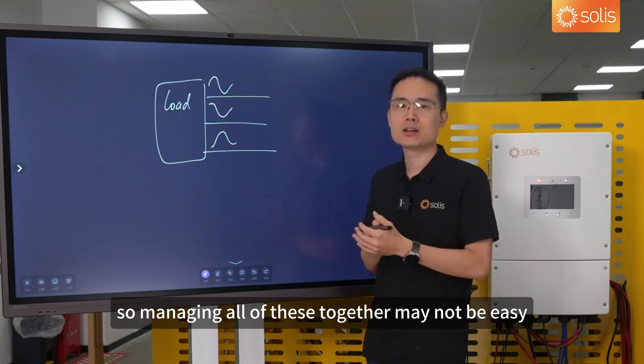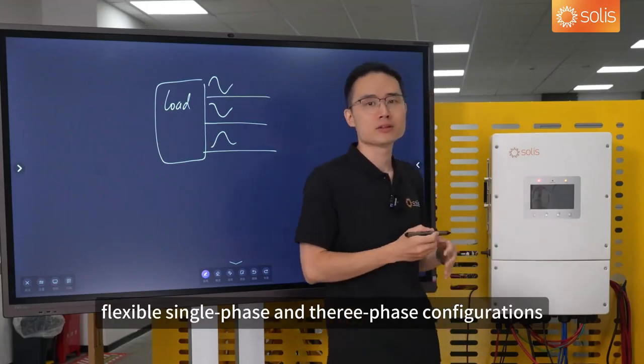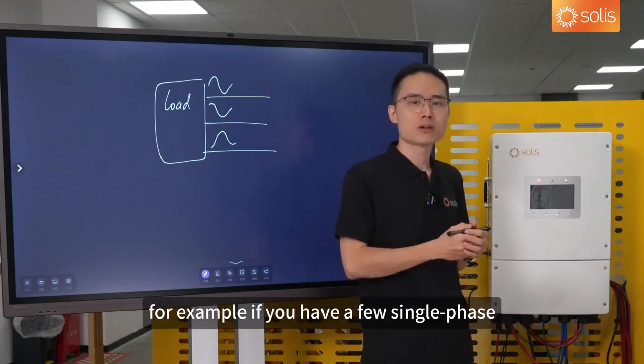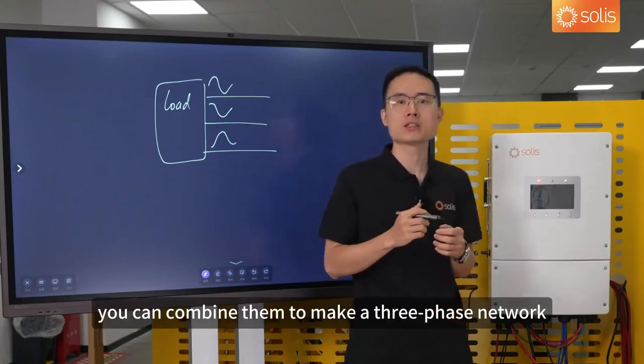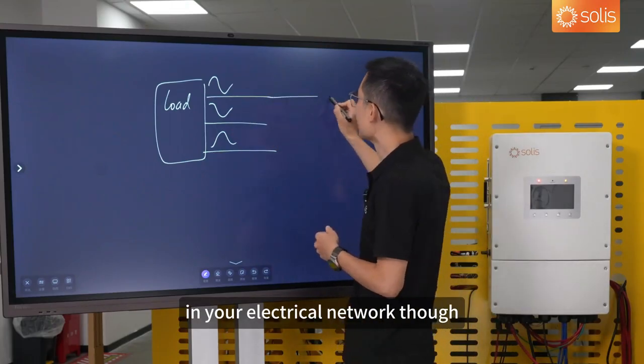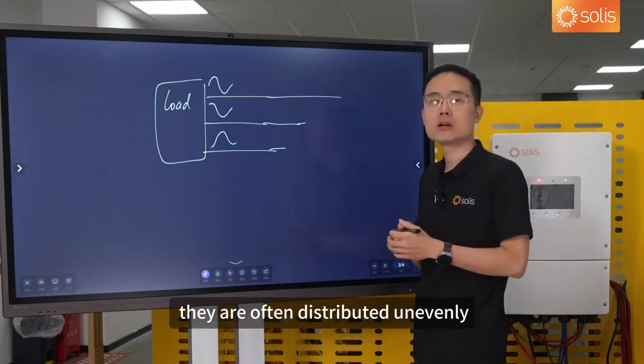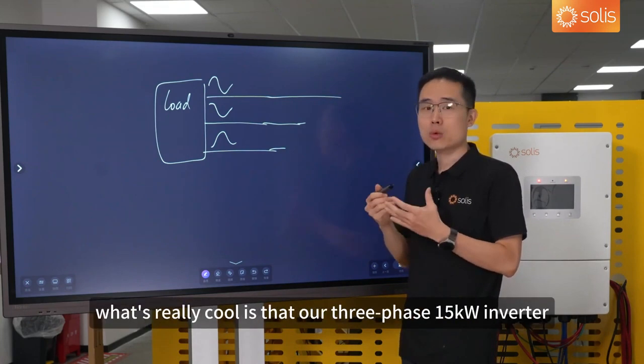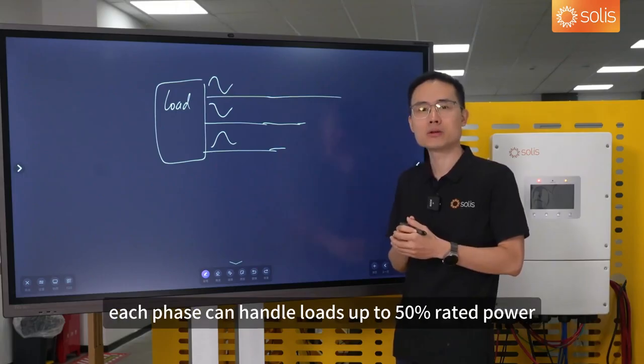Our inverters support flexible single-phase and three-phase configurations, so you can easily connect multiple inverters to create a more powerful system. For example, if you have a few single-phase Solis inverters, you can combine them to make a three-phase network that feeds stable power to your heavy load equipment. In your electrical network, appliances may tap into the three phases separately, and in real life they are often distributed unevenly — which can cause what we call a three-phase imbalance problem. Our 3-phase 15 kW inverter can handle loads up to 50% rated power — 7.5 kW — per phase.